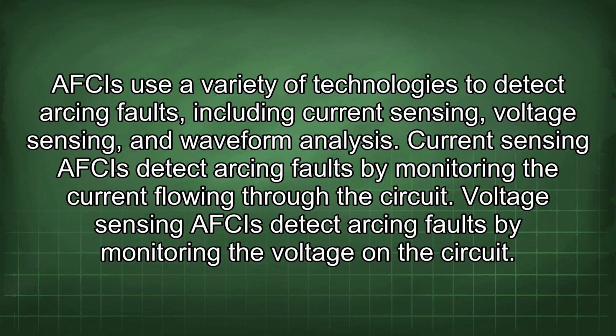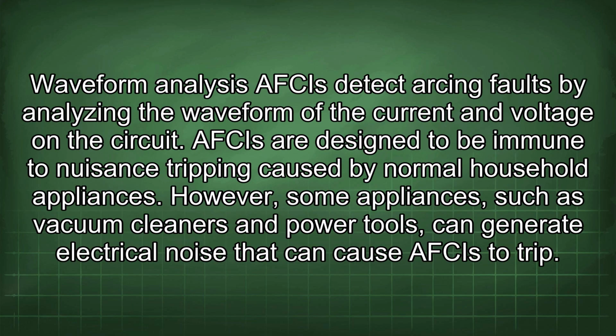Current sensing AFCIs detect arcing faults by monitoring the current flowing through the circuit. Voltage sensing AFCIs detect arcing faults by monitoring the voltage on the circuit. Waveform analysis AFCIs detect arcing faults by analyzing the waveform of the current and voltage on the circuit.